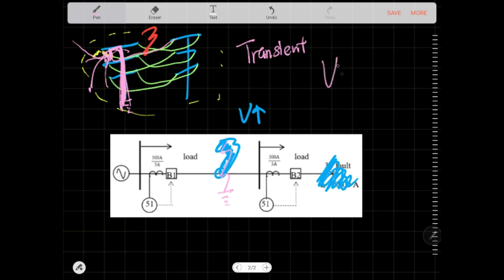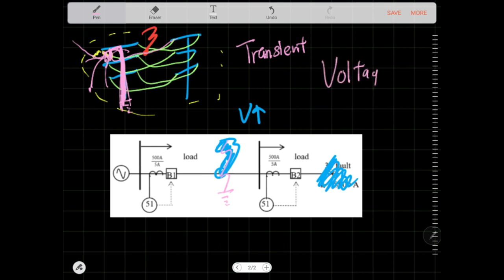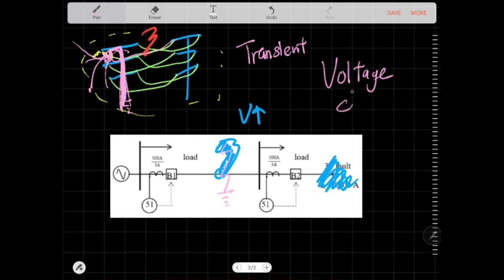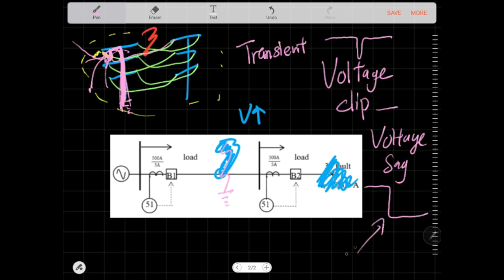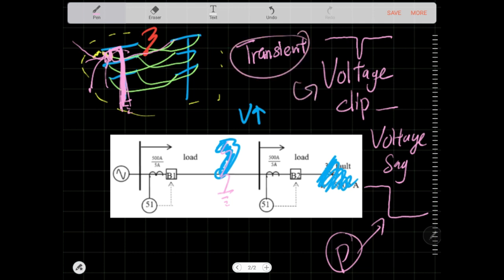A transient fault produces a voltage dip — the voltage is okay, then it suddenly drops and comes back up again. A permanent fault produces a voltage sag — the voltage is okay, then it drops and stays dropped. A permanent fault causes a voltage sag, and a transient fault contributes to a voltage dip.